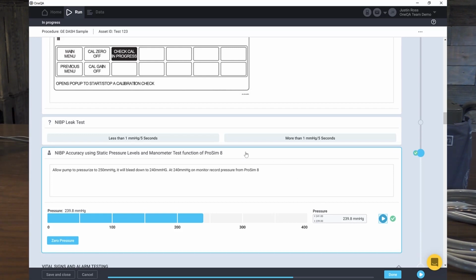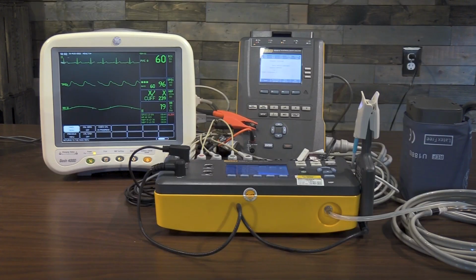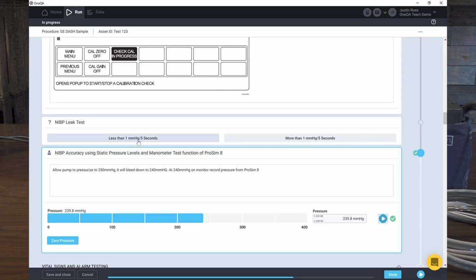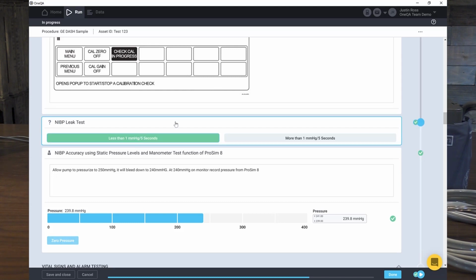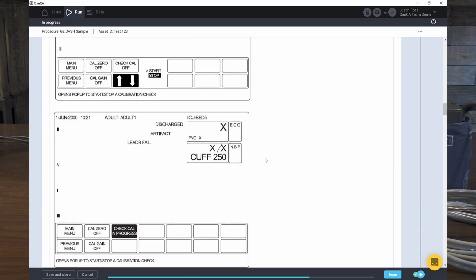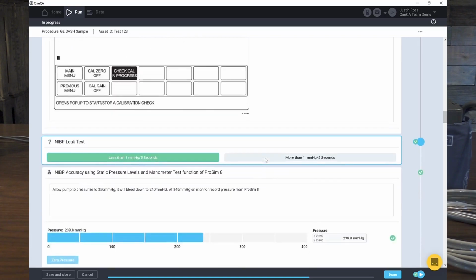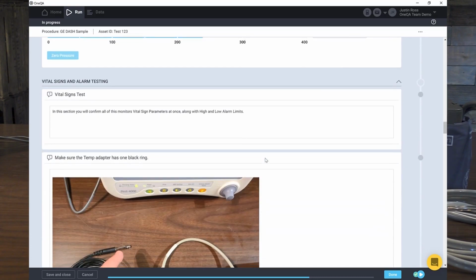Now the next thing it wants us to do is wait after we reach 240 and see if we're losing more than 1 millimeter mercury in 5 seconds. That pressure is holding pretty flat. So I'm going to say yes, we're losing less than 1 millimeter mercury in 5 seconds, which is a pass, which means this test is done and this test is done. So we have our green lights on the right. So now let's move down to the next step.